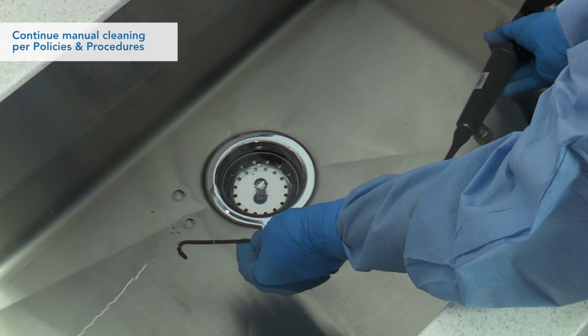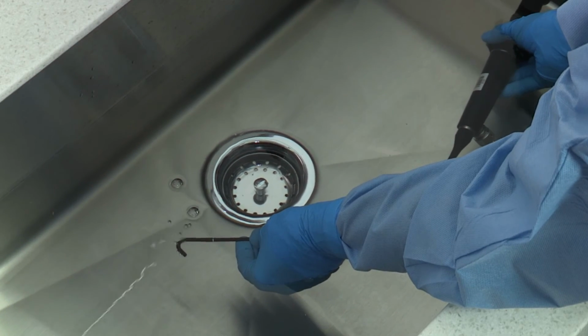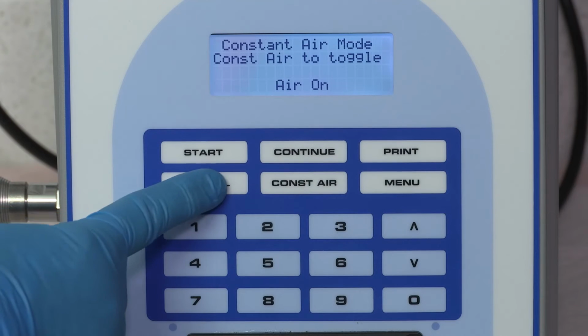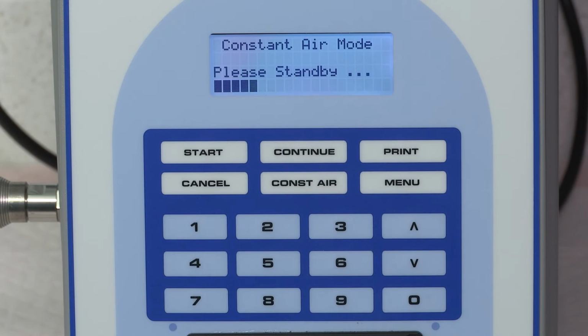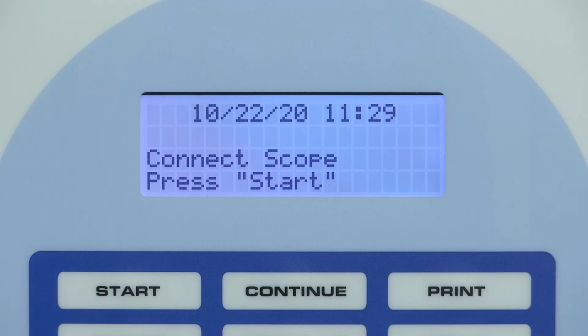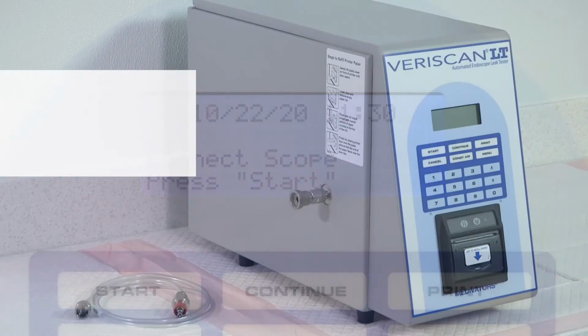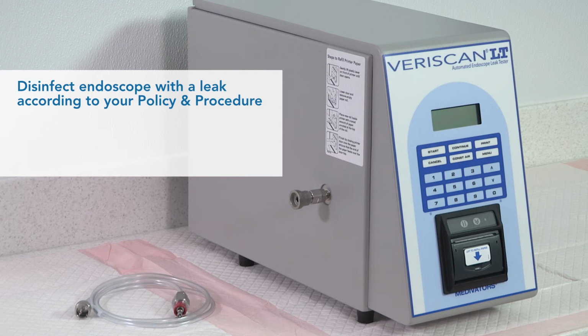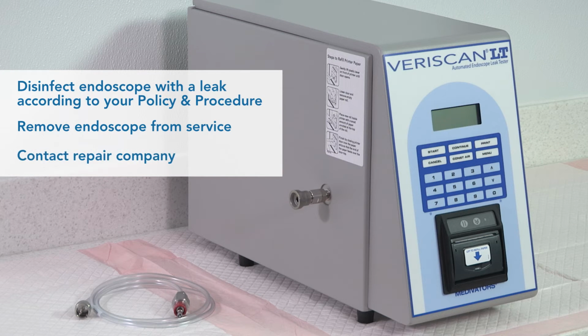Remove the endoscope from the fluid. Press Cancel to halt constant airflow. Once the display shows Connect Scope, press Start. Disconnect the endoscope from the Quick Connect tubing. Disinfect an endoscope with a leak according to your policy and procedure. Remove the endoscope from service. Contact your endoscope repair company to arrange for endoscope servicing.